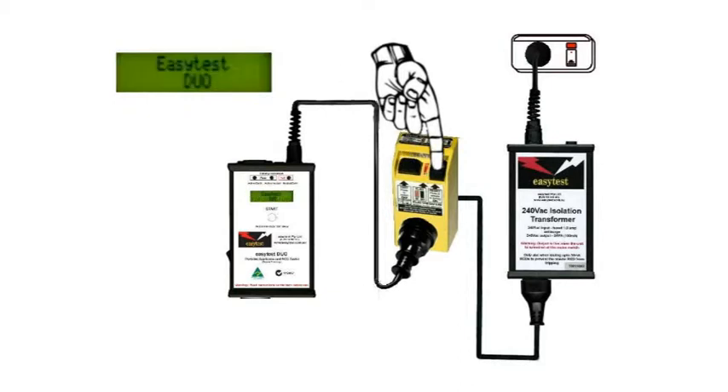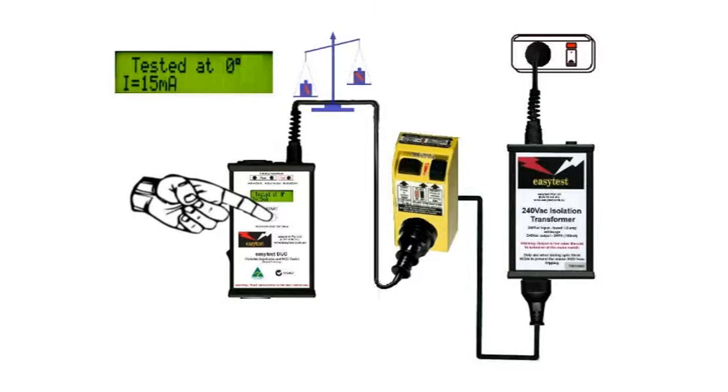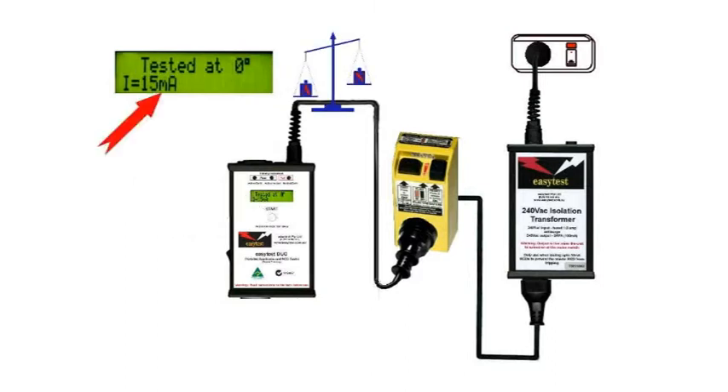Reset the power and it's now time for the Duo to put that unbalanced load on and check the switch times. Press the start button and a 15mA load is applied for a third of a second. If it trips, that's a pass.